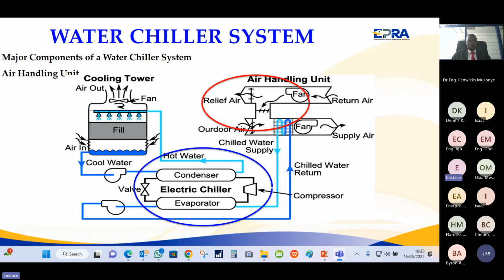Don't touch the fans extracting air and the fans pushing air inside the room. Let them work full blast, that's a security measure. You can have VFDs on them, but it's not very good because you can choke the place. You can play around with the pumping system, the chiller and the cooling towers, because a data center is very critical.